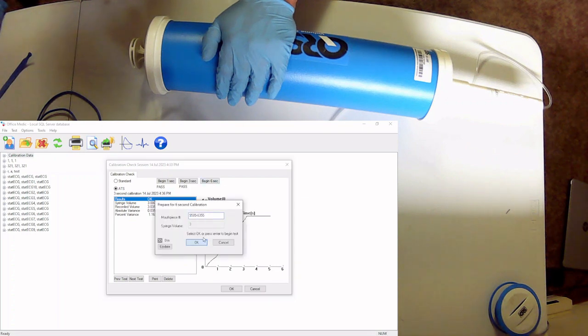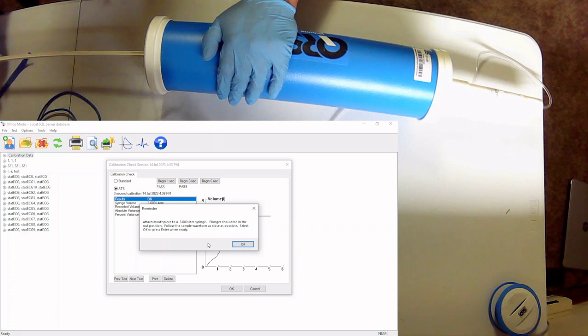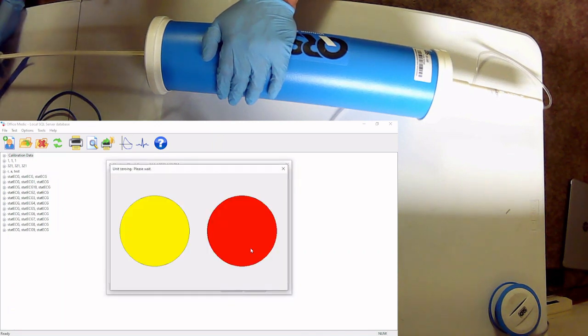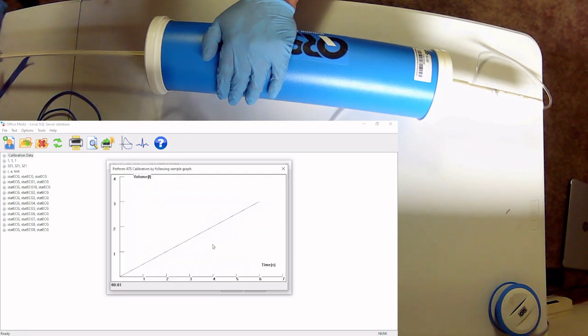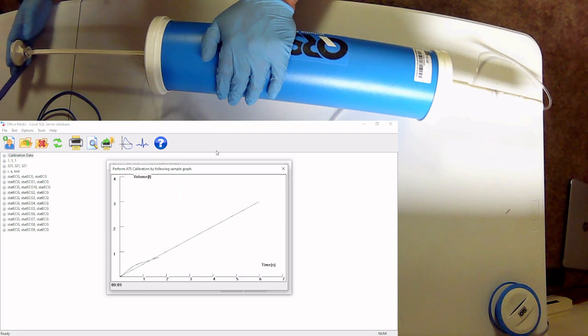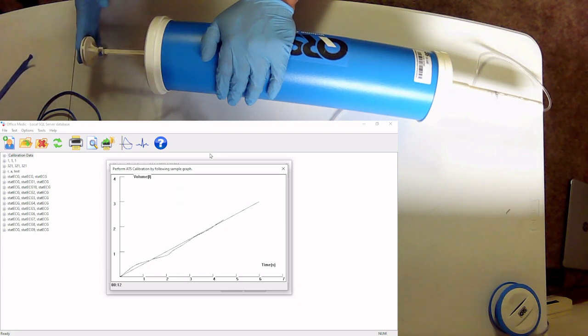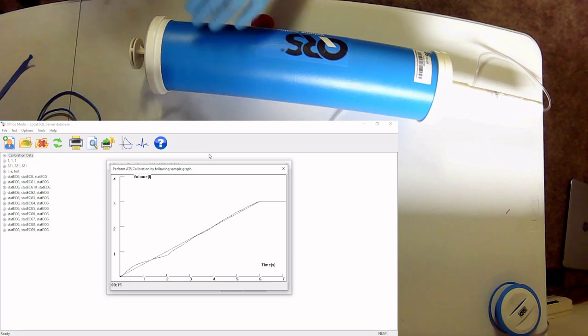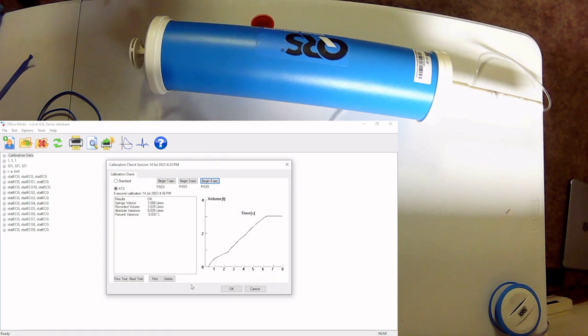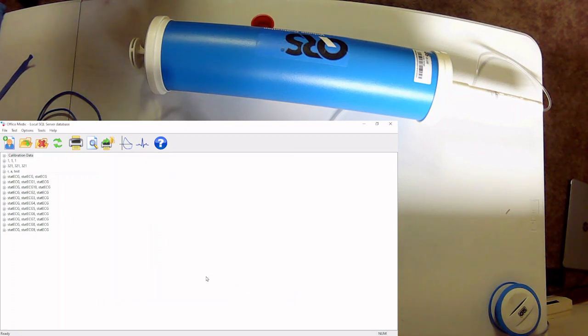We're going to go ahead and do our 6-second test. Make sure our plunger is extended. Click on OK. And now you see this line is even further out. We're going to get 3 liters up to 6 seconds, and we're going to try to follow that line as closely as we can. And again, we pass. All right, so our device is in calibration. We verified that with a 3-liter calibration check syringe. We're going to go ahead and click on OK.